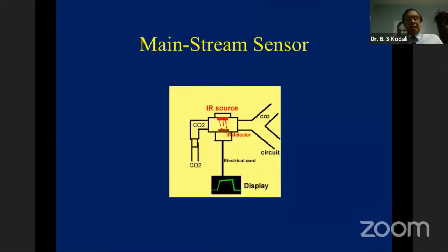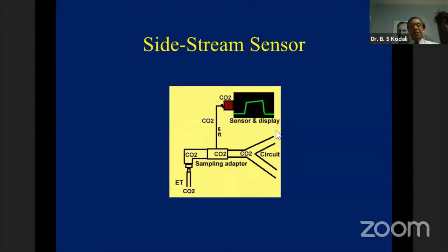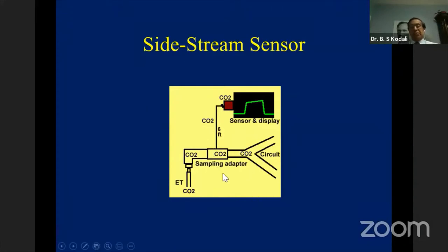There are two sensor types in clinical practice. The mainstream sensor measures CO2 across the airway — the whole cuvette containing the sensor is within the patient airway at the junction of the endotracheal tube and the circuit. In a sidestream sensor, expired gases are drawn via a six-foot tube into the monitor where measurements are made, producing a lag compared to actual respiratory events. The common technology in clinical practice is the sidestream sensor.